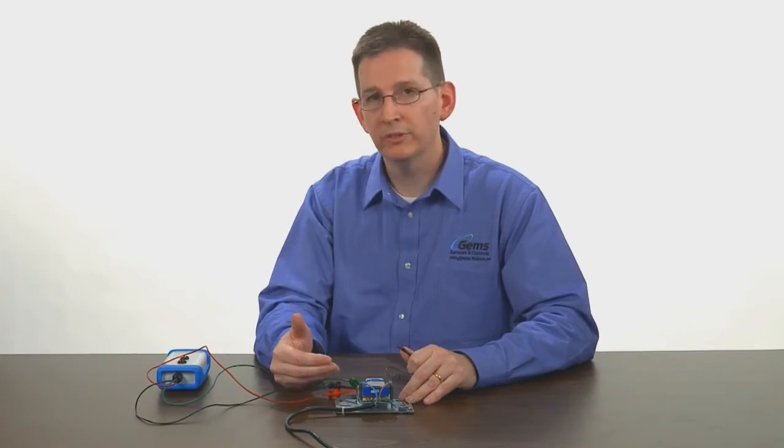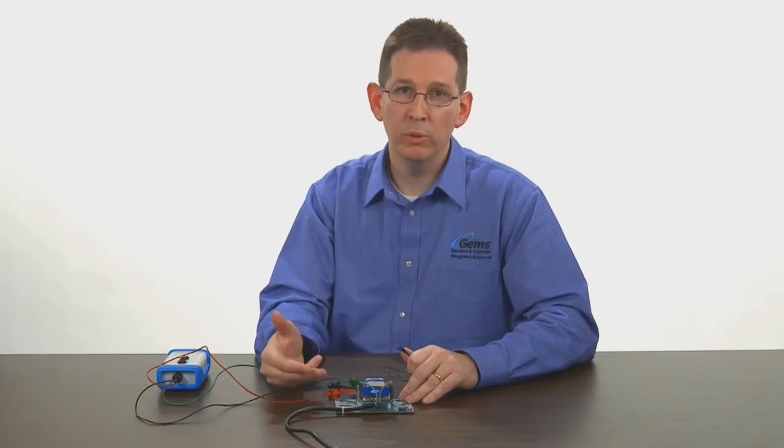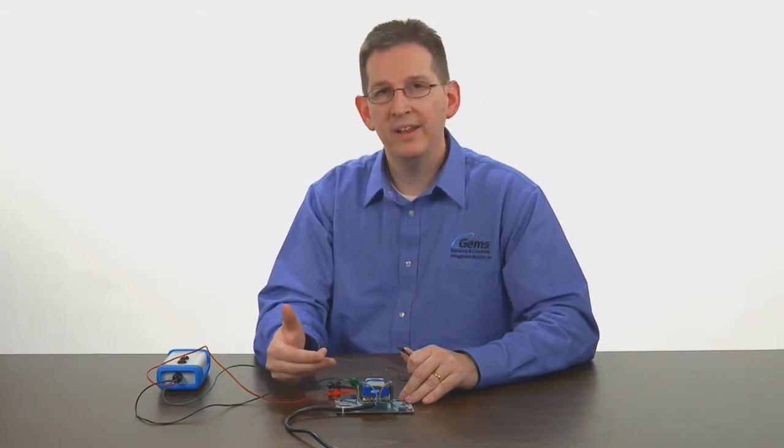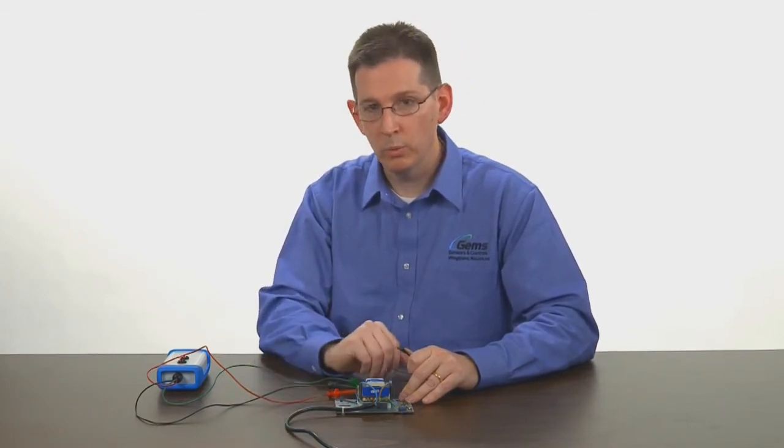For single level service inverse mode the relay is energized when the single probe is dry and de-energized when the single probe is wet.